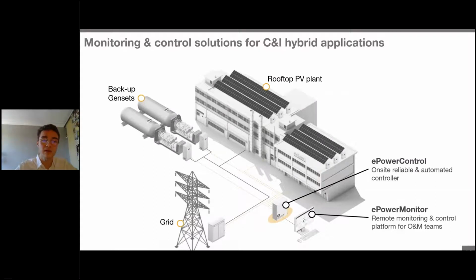So it's key to have this PV-genset controller to ensure a continuous PV production all during the day and during on-grid and off-grid modes and when we have those blackouts. Here, for example, you have an example of a classic on-grid setup. You can see here that we have the grid on the one hand, but also the backup gensets and the rooftop PV plant, or that can be any kind of PV plant connected. Also on this slide, you can see that you have this ePower Control component here that is connected to all of the different power units.